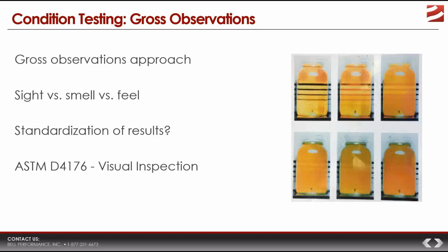And that actually has two procedures that you can run. Procedure number one, some people in the industry call it the swirl test. You take, I think it's 900 milliliters of sample, of course in a clear sample container, and you swirl it so that you create a vortex. And you do that for about 30 seconds, and you hold it up to the light.